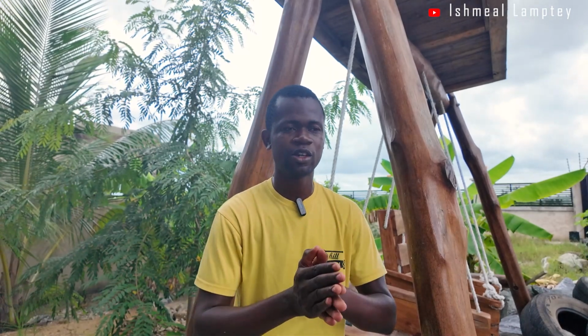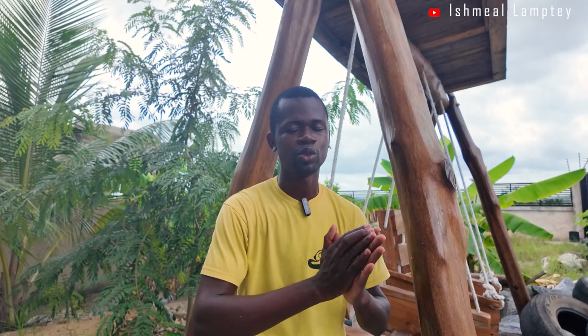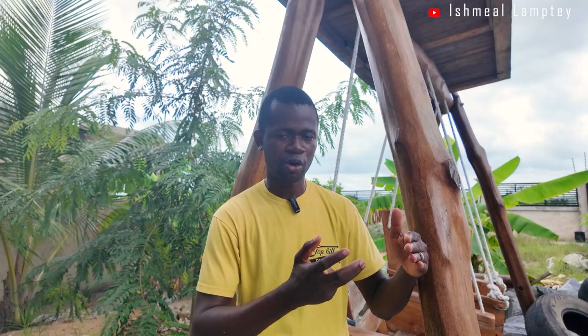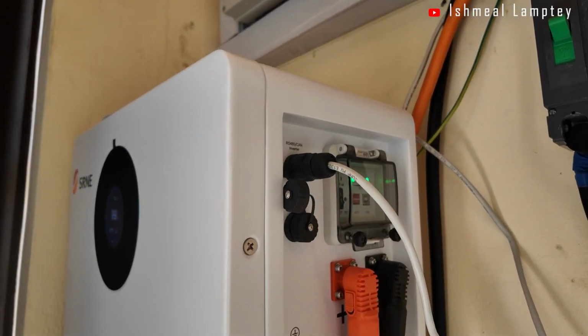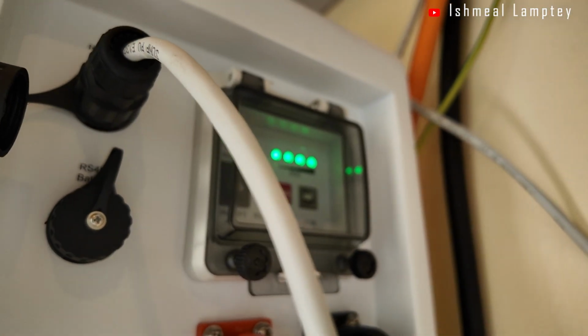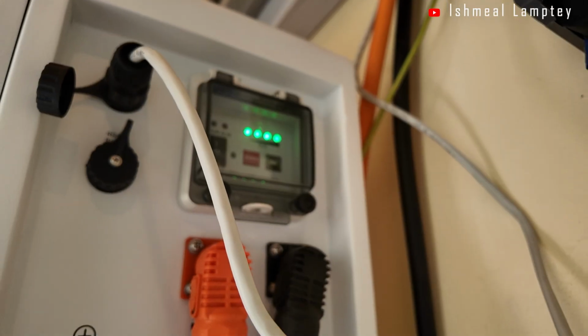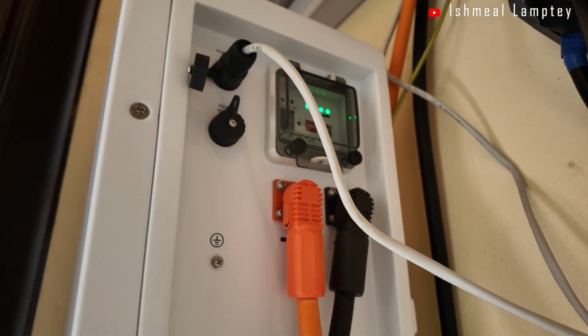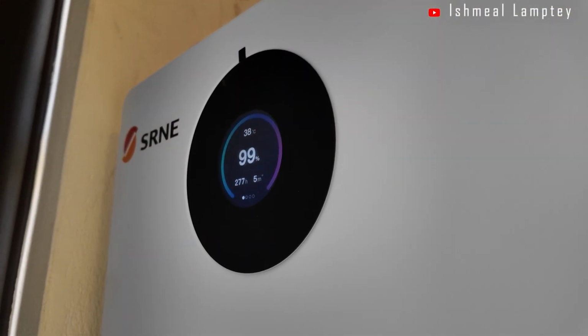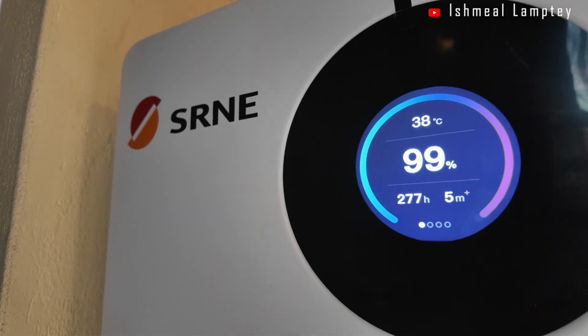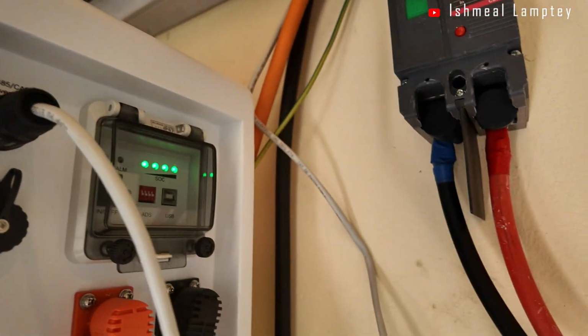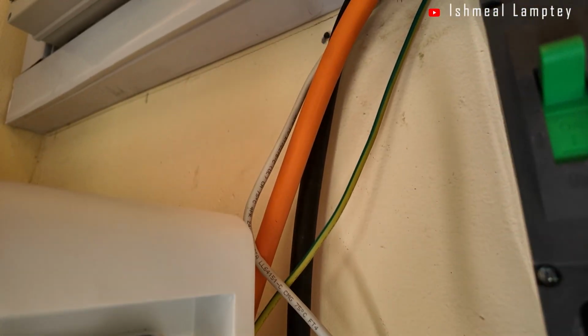As part of the reason why we added the AC input, it is to be able to make the hybrid option of the inverter serve its purpose. So that is why we added the AC input. Then you have the AC output, which is basically the power coming from the solar system going to the house, which is straightforward. And then also, because now you have a backup system, which is basically the battery, you have the power from the battery coming into the inverter. The size of the cable for that was, I think, either 35 mm or 50 mm, one of those. And then that also goes through a breaker. For that breaker, we used a 250 amp breaker, even though the battery also has its inbuilt breakers. Just as I said, it's always best to have an additional layer of protection for some of these systems because of the cost they come with.